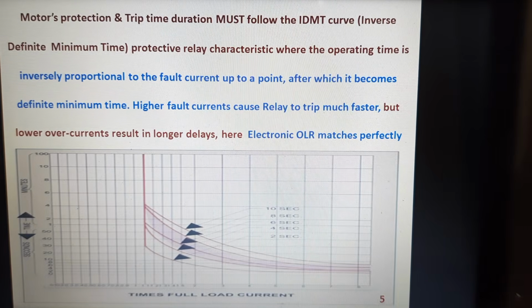The motor's protection and trip time duration must follow the IDMT curve, that is the inverse definite minimum time protective relay characteristic, where the operating time is inversely proportional to the fault current up to a point, after which it becomes a definite minimum time. This is settable from 2 to 10 seconds in an electronic OLR. The higher the fault current, the faster the relay trips, and the lower overcurrents can result in longer delays. The electronic OLR precisely follows the overload and matches perfectly and protects your motor fully.